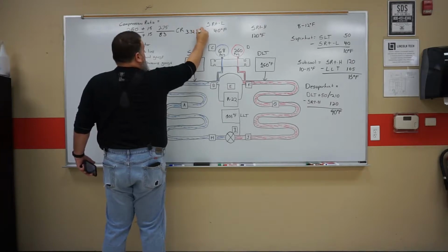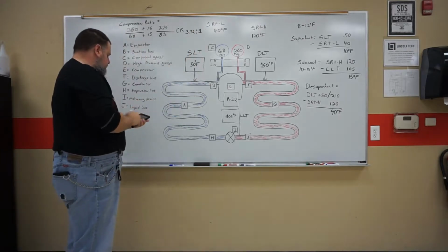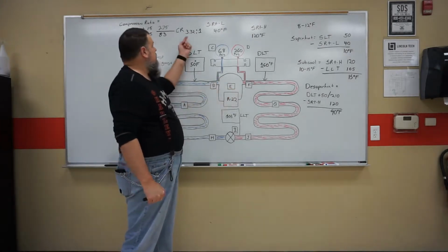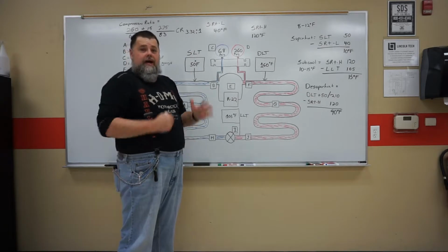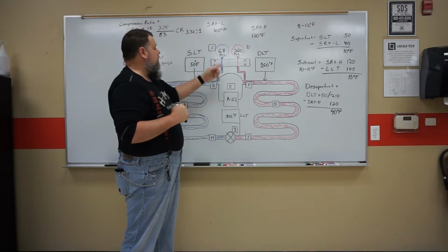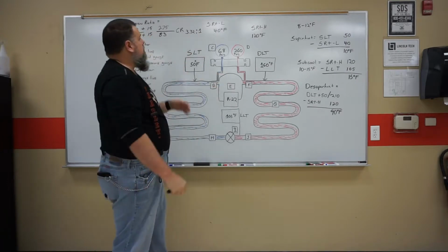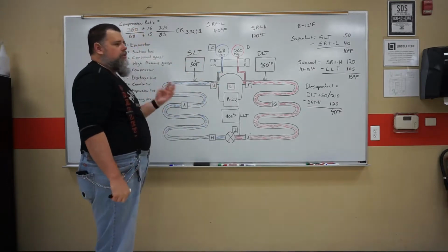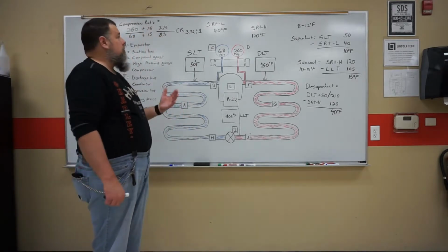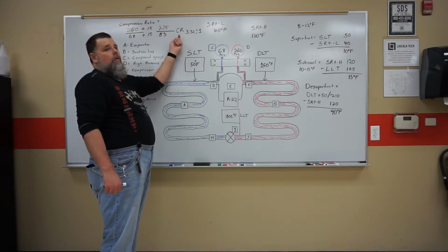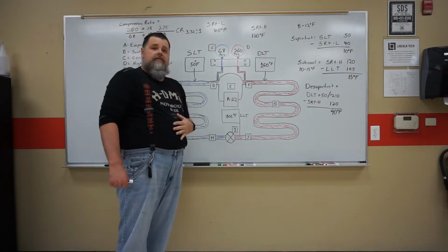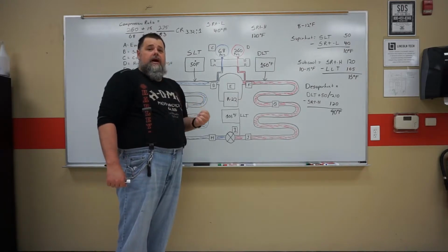1. That means the compression stroke in the compressor is compressing that gas down to the cylinder volume 3.32 times. So it's like you got 3 times the cylinder volume in that one stroke. Now, compression ratios can tell you a different thing. High compression ratios could be 8 to 10 to 1. Low compression ratios could be 2 to 1. That can tell you how your compressor is functioning inside this. So always keep an eye on that.